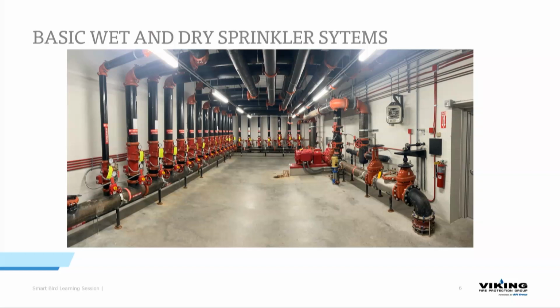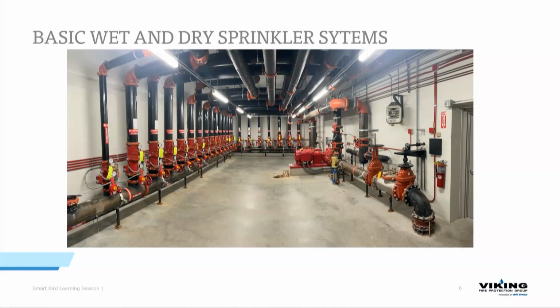And these are all the wet systems that feed into this distribution center. Each one of these risers probably constitutes about 40,000 square feet of physical space that the sprinkler system is covering. So obviously it's a pretty substantially sized building for this amount of wet systems.